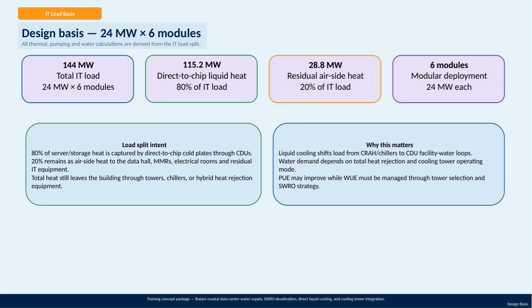This shift influences the overall water demand, which varies depending on total heat rejection and the operating mode of the cooling towers. Finally, while liquid cooling can improve power usage effectiveness, or PUE, it's important to carefully manage water usage effectiveness, or WUE. This is achieved through strategic decisions like selecting appropriate cooling towers and integrating seawater reverse osmosis, or SWRO, to optimize freshwater use. This comprehensive training package, centered around the Batam Coastal Data Center, covers all these aspects, from water supply and desalination to advanced cooling integration.